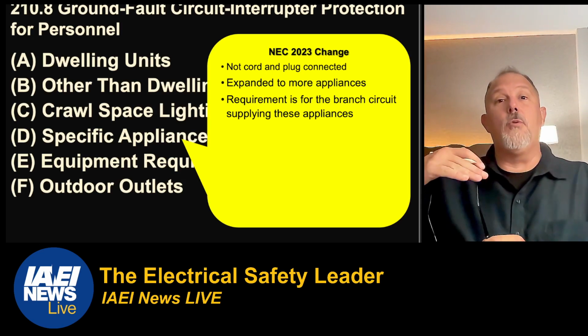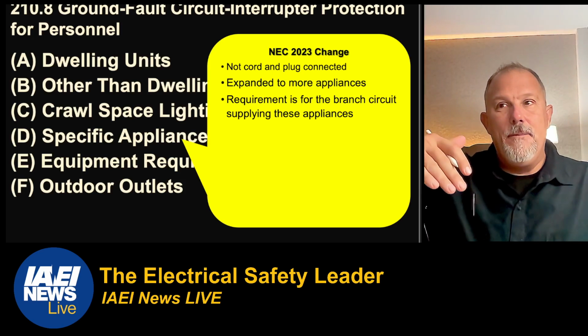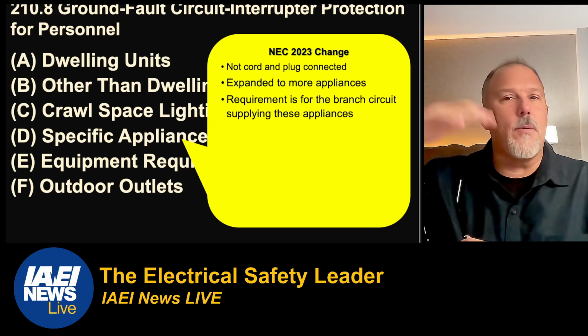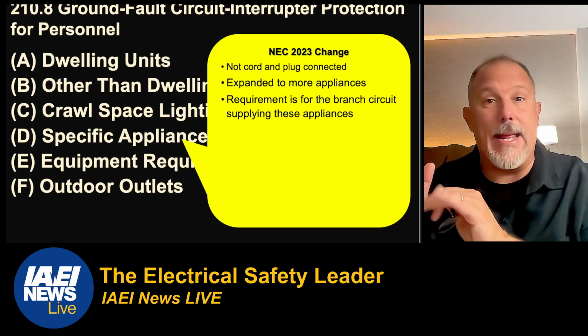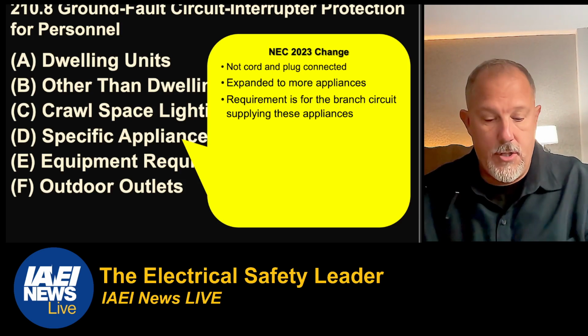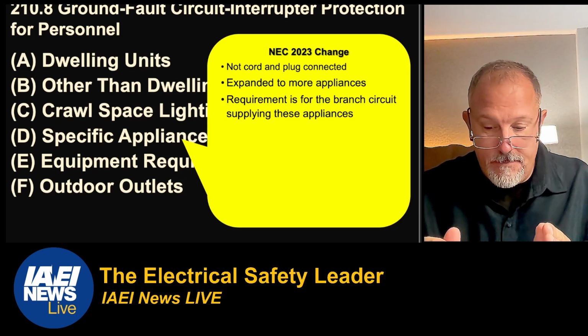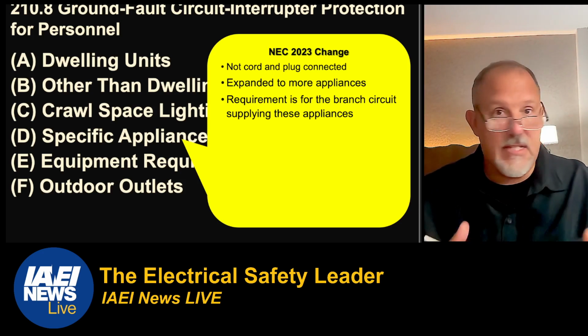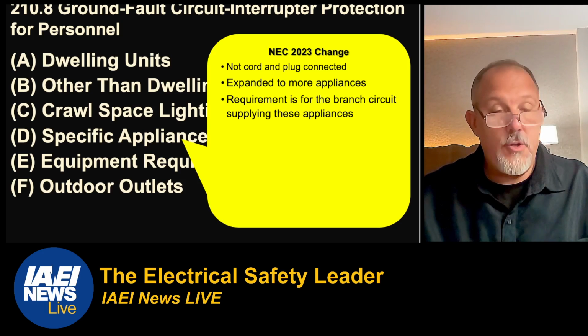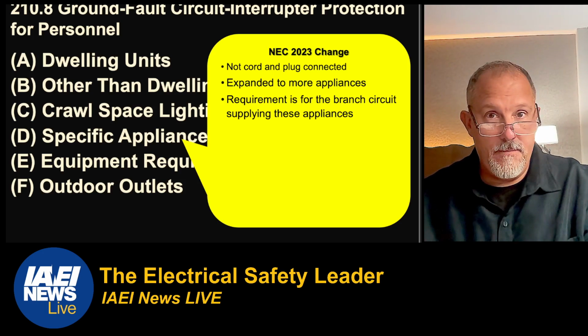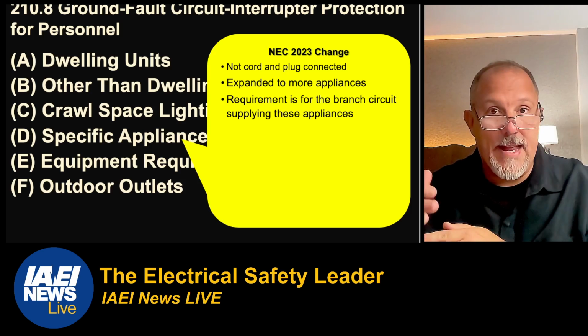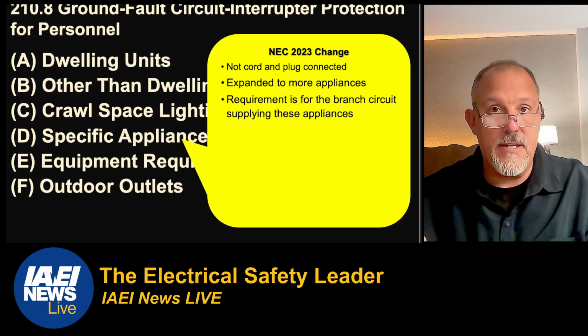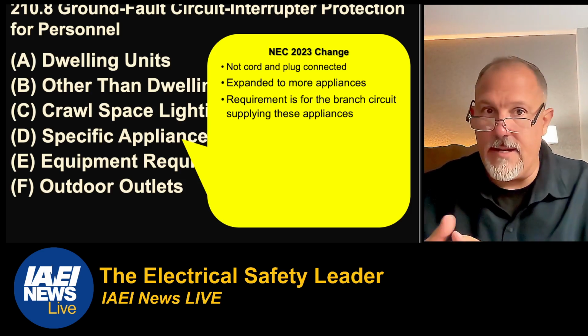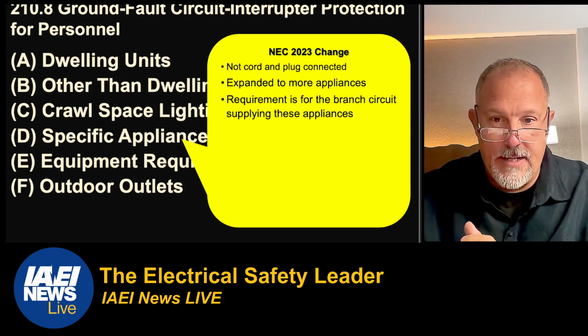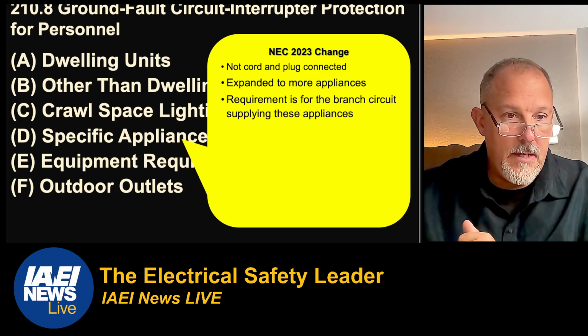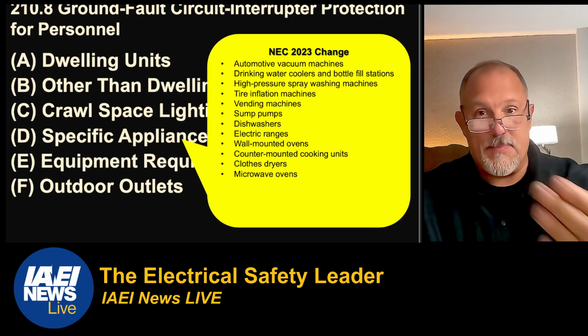So this is the importance of not putting it that way. You can't say, well, that's already covered in 210.8(A), because 210.8(A) only covers receptacles. This is any outlet supplying a list of appliances. You have to provide GFCI protection for that outlet that is supplying these appliances. And we created the list, and we've expanded it.